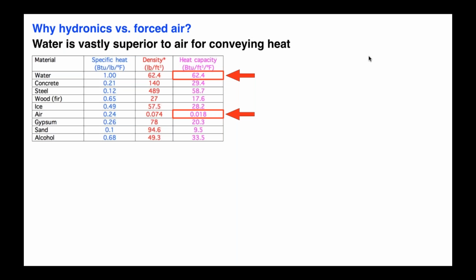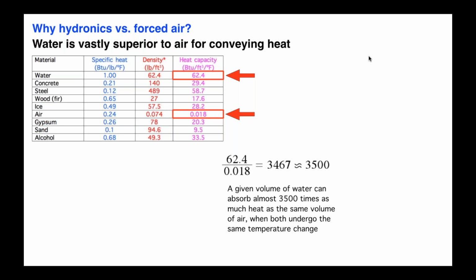So we look at these physical properties of water versus air. These are nothing you can change. This is simply what we're given to work with. So when you make a comparison, I like to do a ratio. If I take the heat capacity of water and divide it by the heat capacity of air, and round up, it's almost a factor of 3,500. So what does that mean? It means a given volume of water can absorb almost 3,500 times as much heat as the same volume of air for the same temperature change.